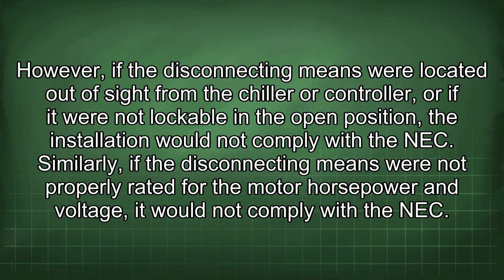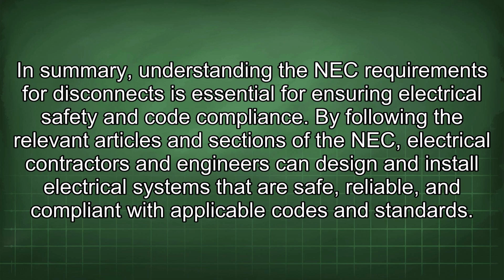However, if the disconnecting means were located out of sight from the chiller or controller, or if it were not lockable in the open position, the installation would not comply with the NEC. Similarly, if the disconnecting means were not properly rated for the motor horsepower and voltage, it would not comply with the NEC. In summary, understanding the NEC requirements for disconnects is essential for ensuring electrical safety and code compliance.